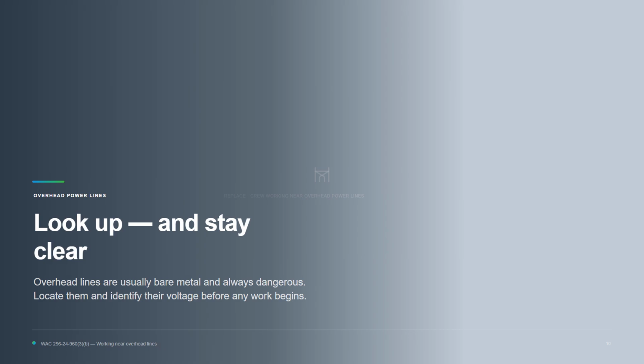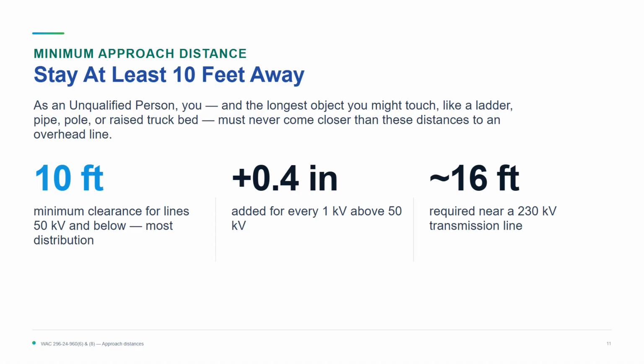Overhead lines are usually bare metal and always dangerous. Before any work, locate them and find out the voltage. The next slide gives you the distance to keep. The rule for unqualified workers is simple: 10 feet from any overhead line at distribution voltage. That distance applies to you and to the longest thing you might be holding: a ladder, pipe, pole, or a raised truck bed. Higher voltage means more distance.